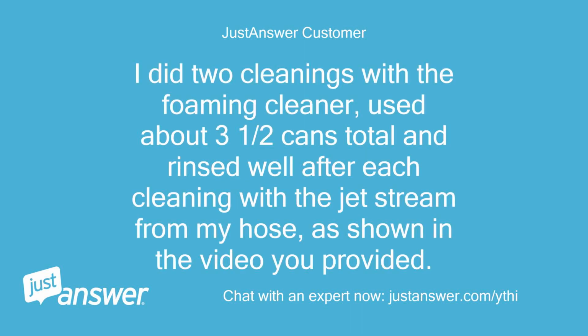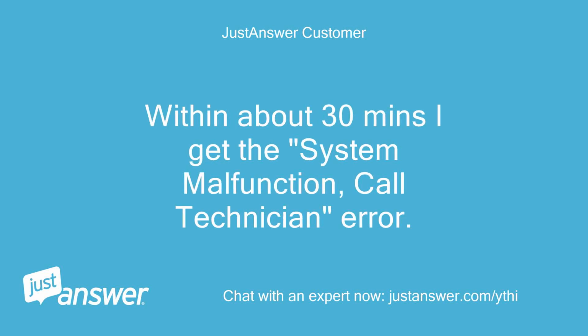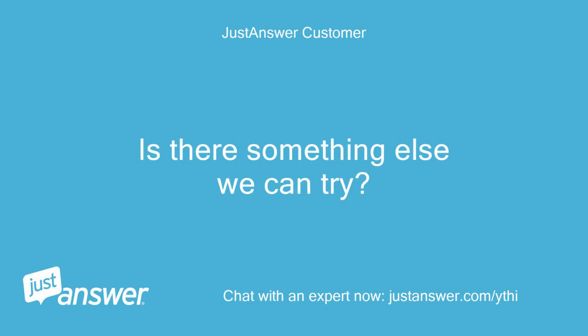I did 2 cleanings with the foaming cleaner, used about 3.5 cans total and rinsed well after each cleaning with a jet stream from my hose, as shown in the video you provided. I let the unit dry for an hour and then flipped the circuit breakers back on. Within about 30 minutes I get the system malfunction. Fault code says high thermal cutout, 32 events, and high comp cutout, 10 events. Is there something else we can try?